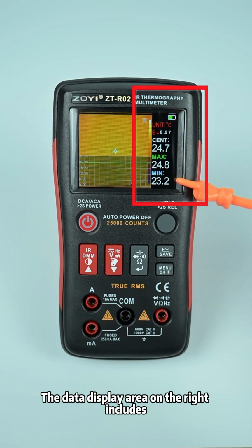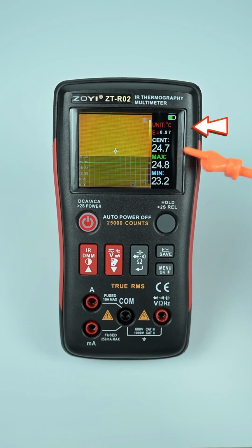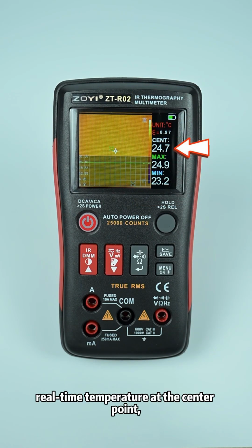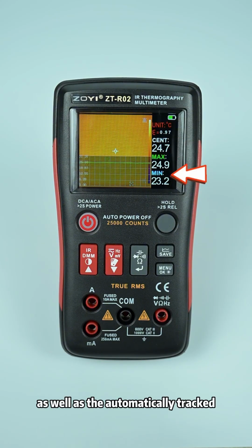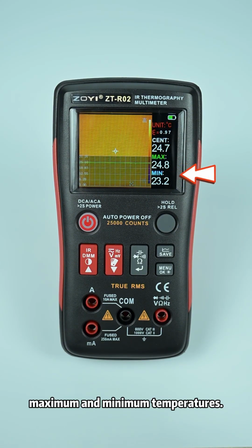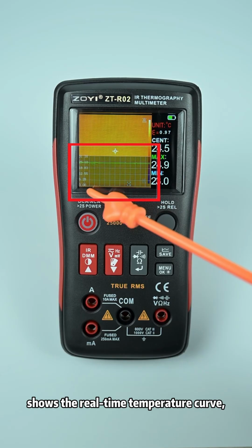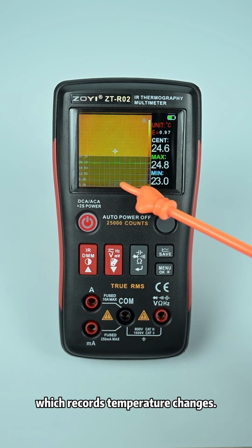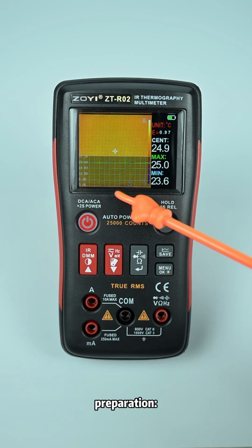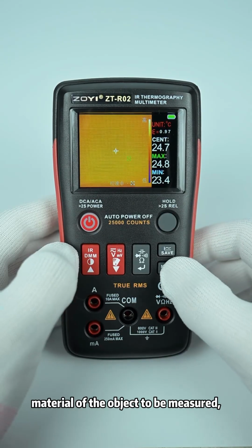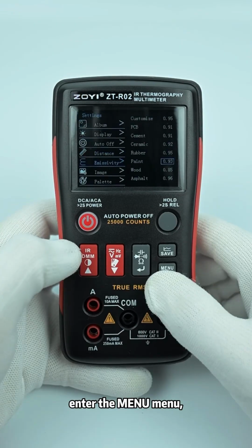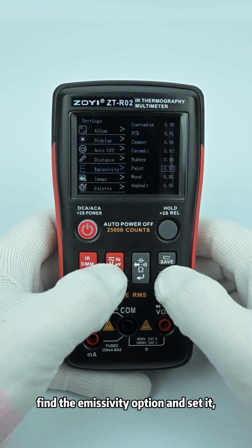The data display area on the right includes the battery icon, temperature unit, emissivity, real-time temperature at the center point, as well as the automatically tracked maximum and minimum temperatures. The lower left corner of the image shows the real-time temperature curve, which records temperature changes. Temperature measurement preparation. First, according to the surface material of the object to be measured, enter the menu, find the emissivity option, and set it.